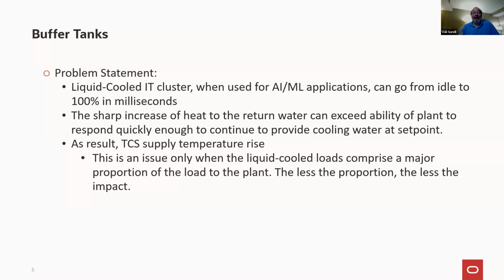So the following question is, how often does it happen? Does it go up to 100% and stay there for an hour? Or does it go up to 100% and stay up there for 10 seconds? From the mechanical or infrastructure point of view, it makes a huge difference, because if it stays up at 100% for 10 seconds, the impact to the plant is dampened quite a bit. But if it stays up there for an hour or longer, or however long the residence time of the water in the system, it has an absolute impact on the chiller plant.